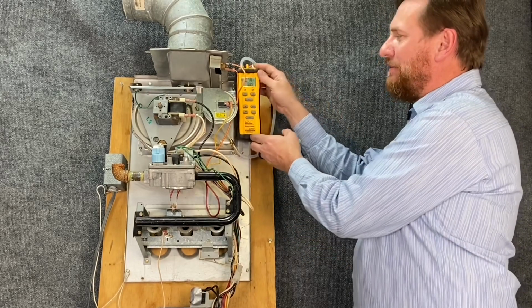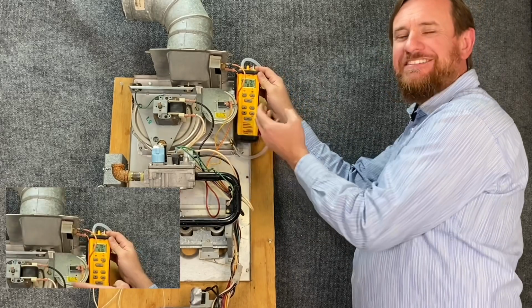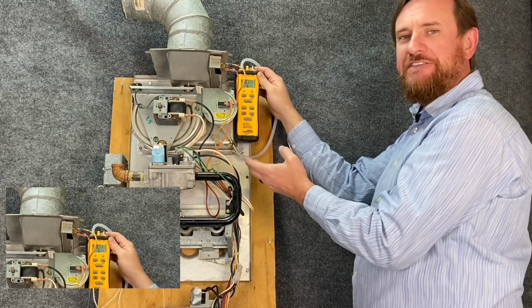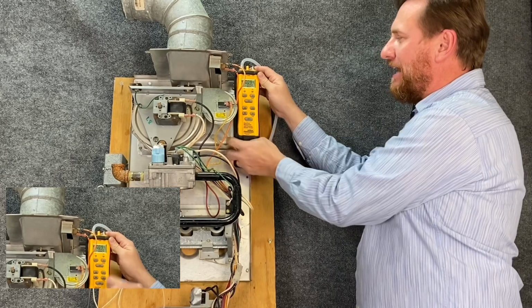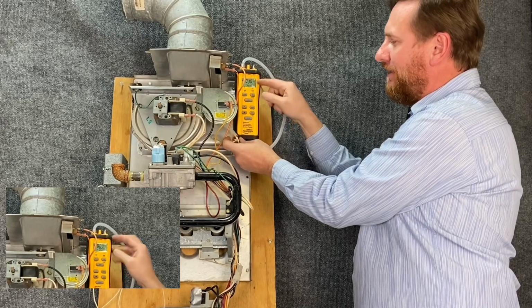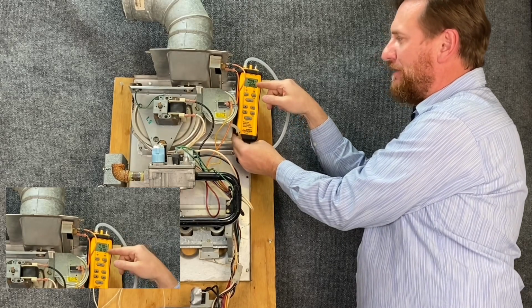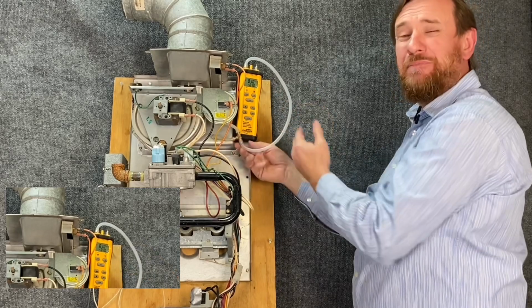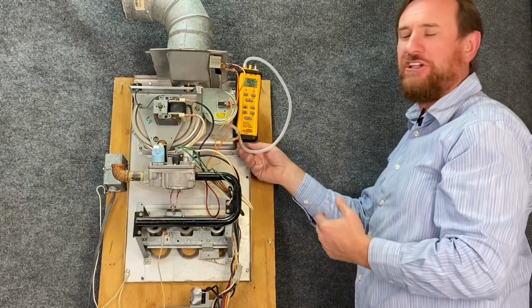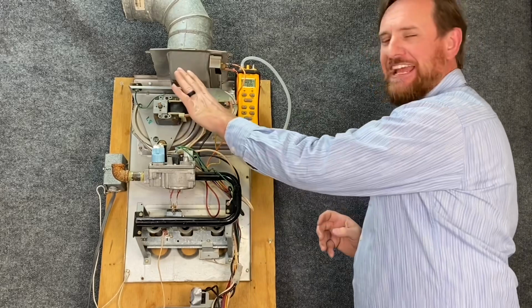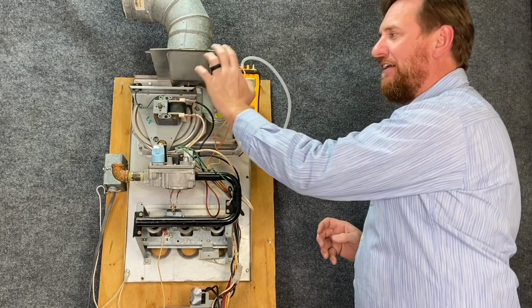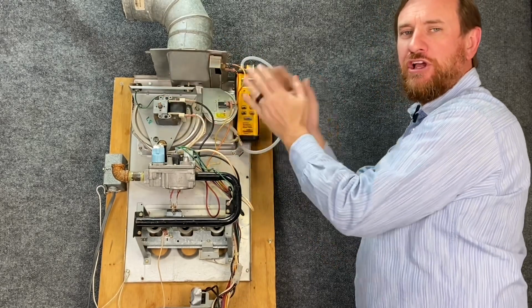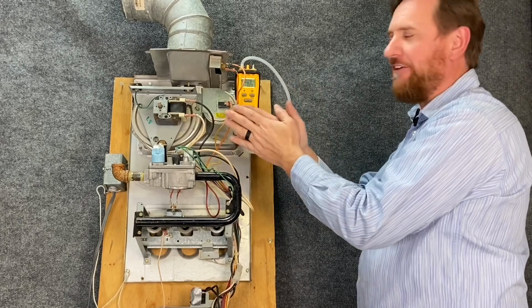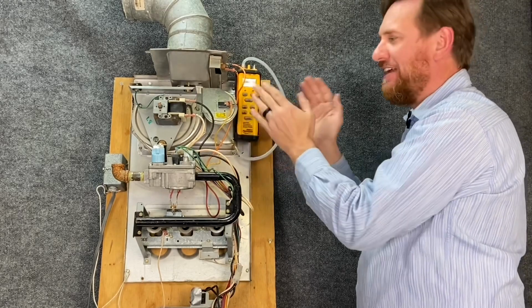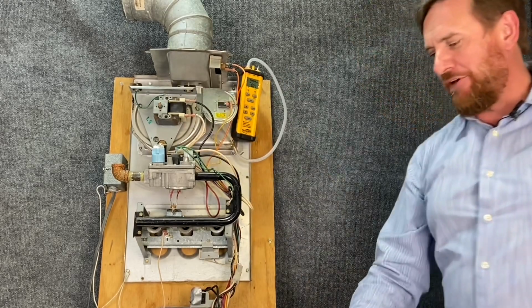In this case, we need to be thinking, my switch isn't closing, it's a vacuum pressure switch. Do I have enough vacuum? And the answer is no. I only got 0.1 inches of water column. In this case, it's jumping around a little bit, but 0.1 inches of water column. I need 0.25 inches of water column for this to close. So I need to be looking on the fan side. What's going on here? Let me check that inducer fan motor, go through all the process to make sure that's working first. It's not a problem with my switch. It's on this side. So I want to make a minor adjustment to this unit.